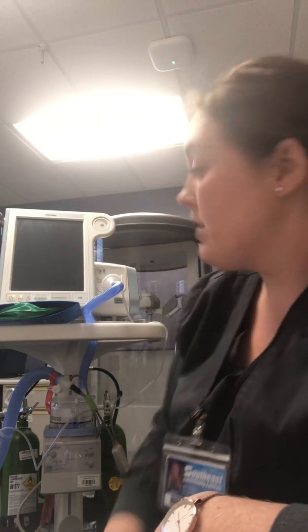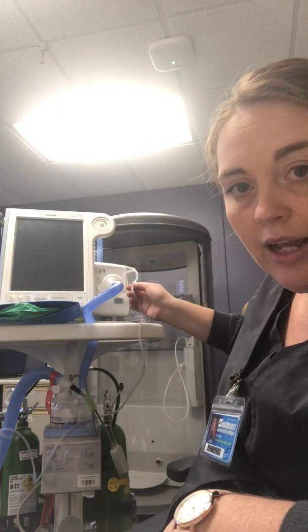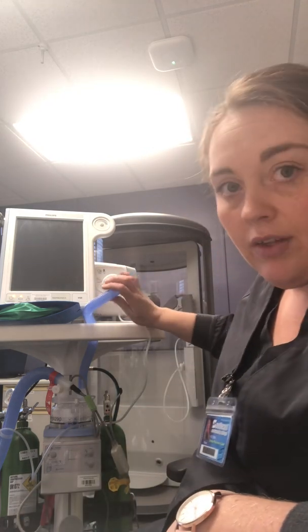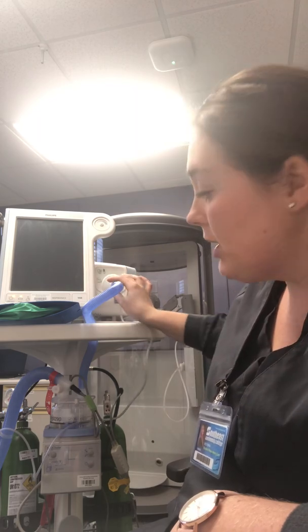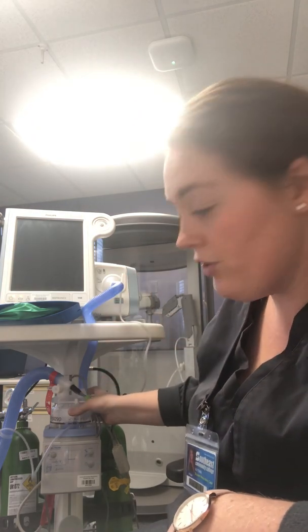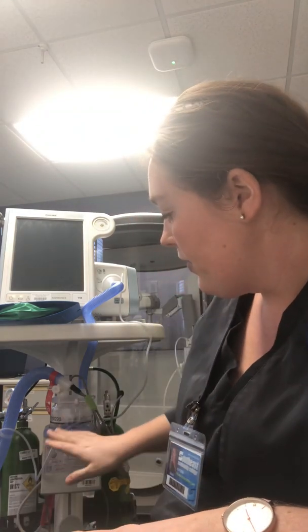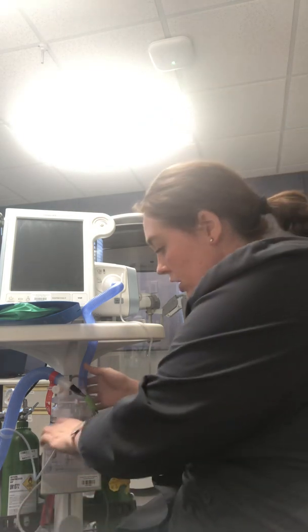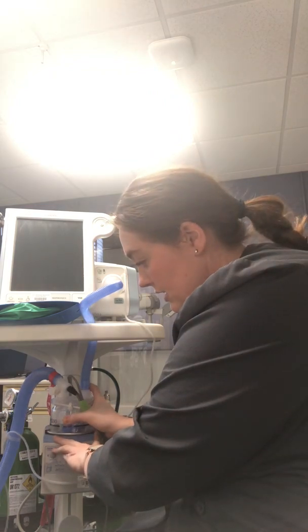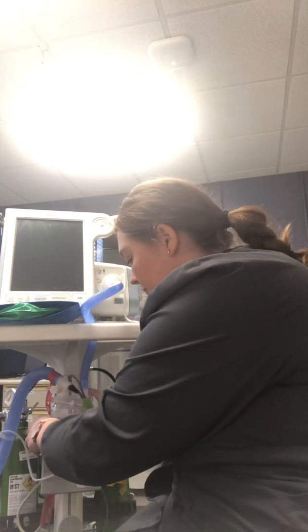So looking on the outside part, you can see this thin line. This is pressure, the pressure that's going to go to your patient, and then this is part of the heated humidity. So this is going from the machine and it's coming down here into the chamber. I do have this little spike, and that's what we use. We spike this bag of sterile water for oral inhalation. The water then fills in this little Fisher-Paykel chamber, which you can attach and detach just by sliding it in and out, just like so.